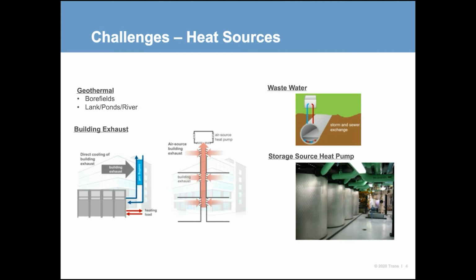The last one, storage source heat pump. This is an interesting one that we're seeing in bigger cities. If you have a building that goes from heating and cooling through the course of a day, this would be a great setup to try to conserve all your BTUs from the building. So the setup would be in the morning. Let's say you have morning warm up for an office building. In the morning, you're going to run a chiller and make ice. You're going to build ice, and you're going to take that, what would go to the cooling tower, that rejected heat, and you're going to send that to the building for your heating loads. And then as the building transitions throughout the day into cooling mode, that's when you're going to start to melt the ice. All right, so you're going back and forth with your BTUs throughout the day from ice to no ice. All right, but in general, there's a lot of cool strategies going on for electrified designs on where we can pull heat.